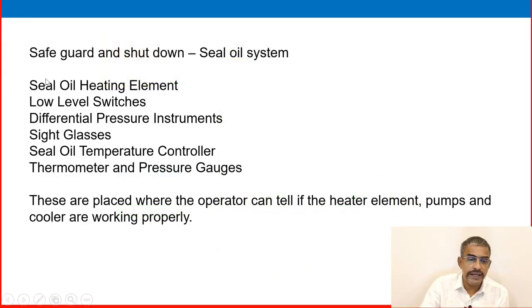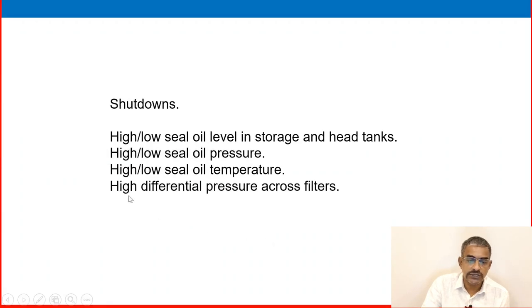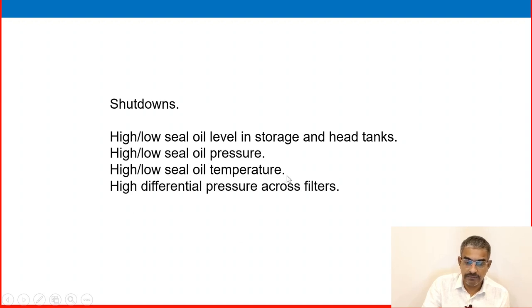Seal oil system shutdowns include: seal oil heating element failure, low level switches, differential pressure instruments, sight glasses, seal oil temperature controller, thermometers, and pressure gauges to tell if the heater elements, pumps, and coolers are working properly. Shutdowns can occur on high and low seal oil level in the storage and head tank, high and low seal oil pressure, high and low seal oil temperature, and high differential pressure across the filter.